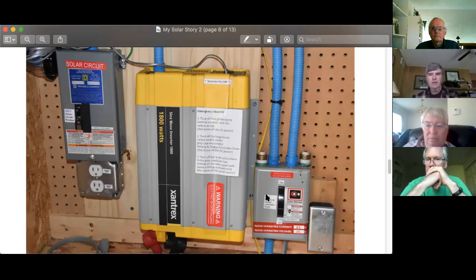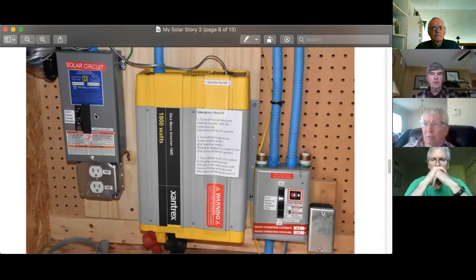This is a little fuse box over here with standard fuses in it to protect from any kind of over voltage, both input and output to the inverter. I also have another lightning arrestor over here on the AC side, as well as a ground fault and arc fault interrupter circuit breaker for safety's sake and to protect equipment that's plugged in here, since what I have plugged in here is worth protecting with some equipment.